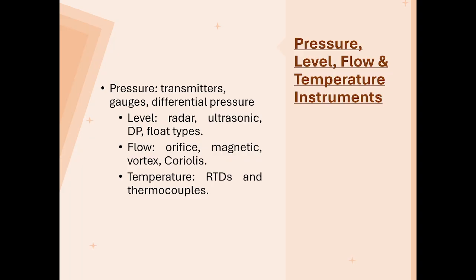So to measure these variables, we use instruments. All right, so instruments are measurement devices. Now, pressure can be measured using gauges and transmitters. Level can be measured using radar, differential pressure, or float-based instruments. Then for flow measurements, it depends on the process conditions. So we could use an orifice plate or a magnetic meter, a vortex or Coriolis meter. While temperature is commonly measured using RTDs, that is resistance temperature detectors, transmitters and thermocouples. All right. Now at this stage, I don't expect you to know how each one works internally. What I want you to understand is this: if the measurement goes wrong, every control decision that follows will also be wrong. All right, so once measurements are taken, the plant must act on those measurements.